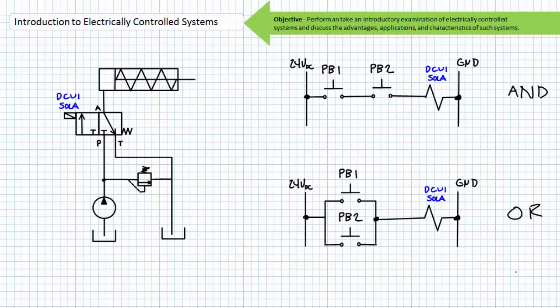Alternatively, consider two switches, push button 1 and push button 2, wired in parallel with each other. This is the logical OR operator. The solenoid would energize if push button 1 only was closed, if push button 2 only was closed, or if they were both simultaneously closed. This is a common feature for a device that requires an operator to energize the solenoid of DCV1 Sol A from two different locations. An example might be a hydraulically driven lift with two independent control points.